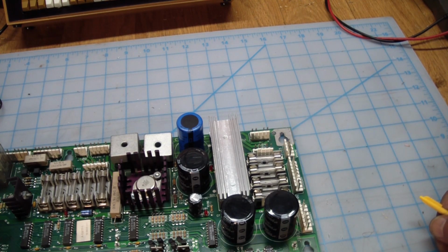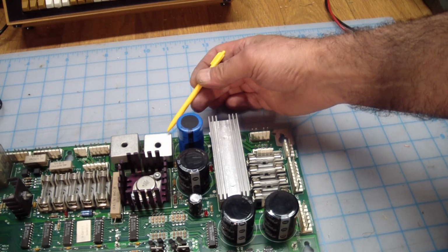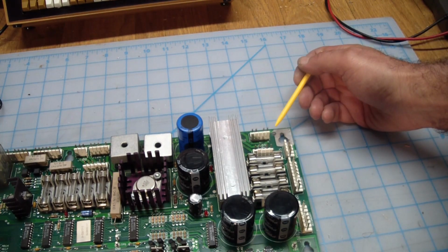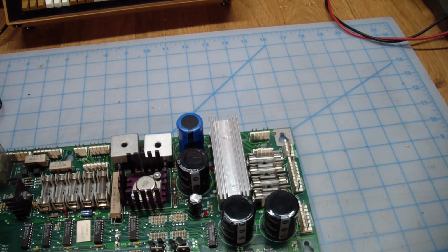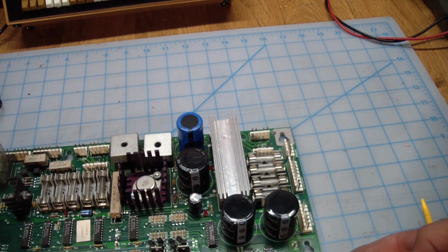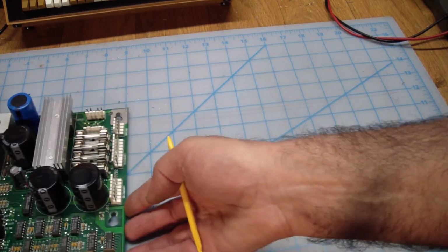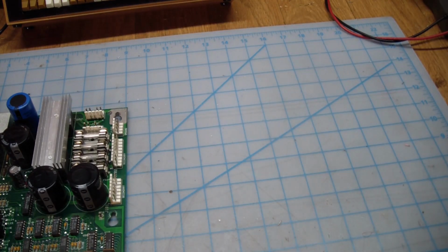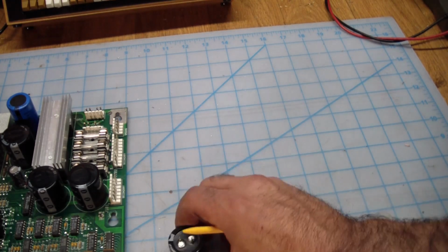So I went in there, did continuity checks, and the DC output of the bridge and ground were at a dead short. That didn't leave a whole lot of guesswork — there wasn't much room left for what could possibly go wrong. I measured it on the board, and yes, there was a dead short.